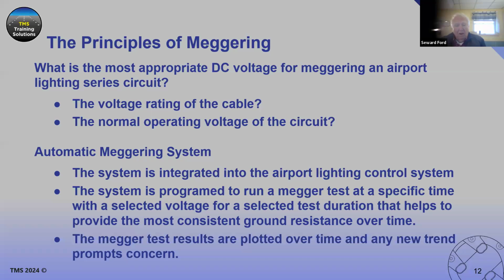We also have automatic Meggering systems, and many manufacturers offer them. They're integrated with the CCR and the control system you have, and the system is programmed to run a megger test at a specific time with a selected voltage for a selected test duration. That helps provide the most consistent ground resistance over time, and that's what we're looking for, history.